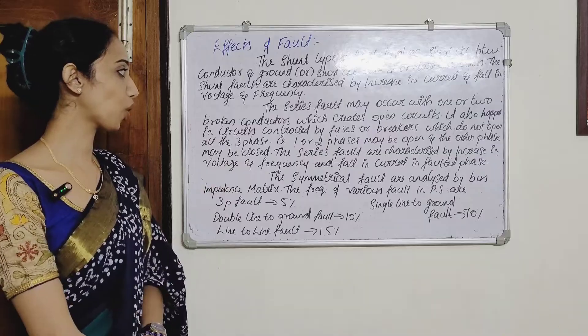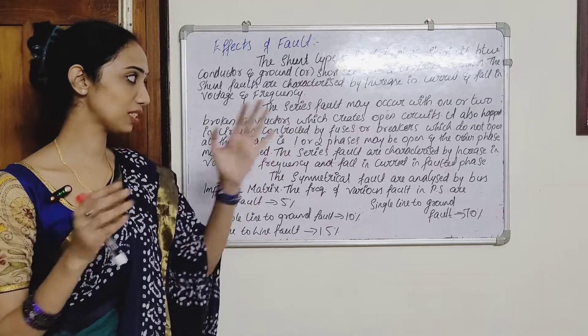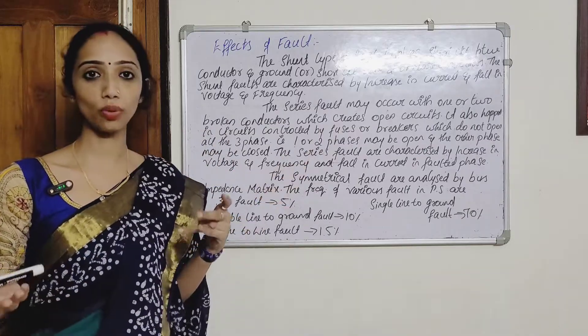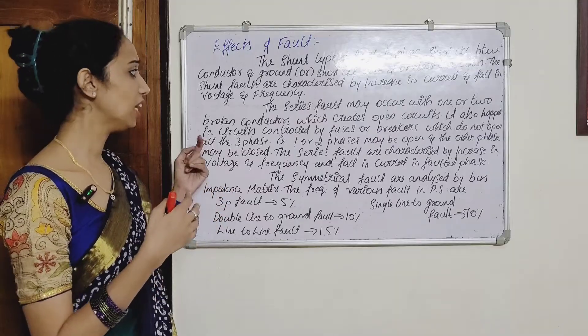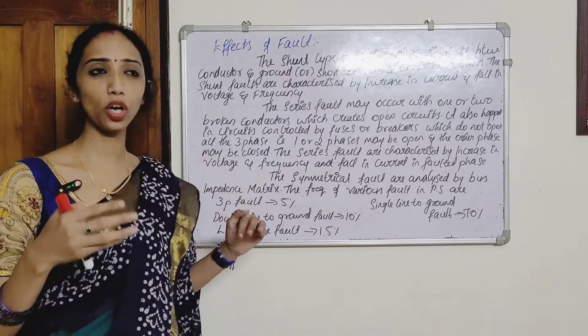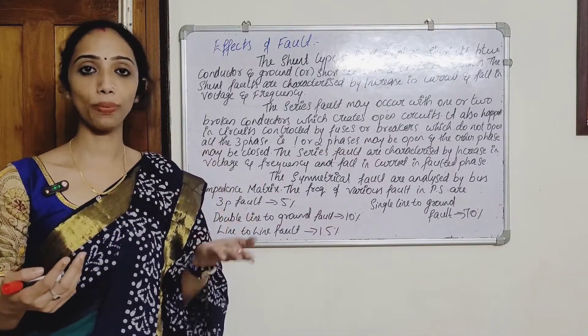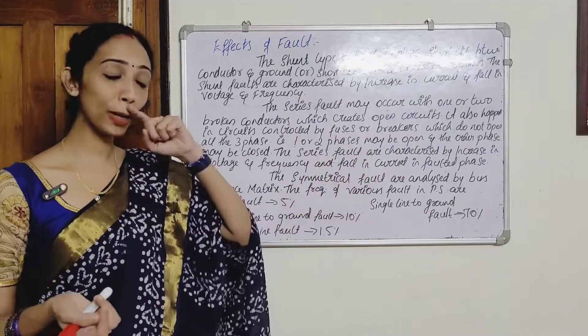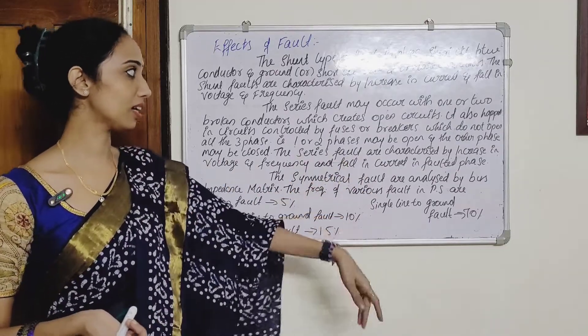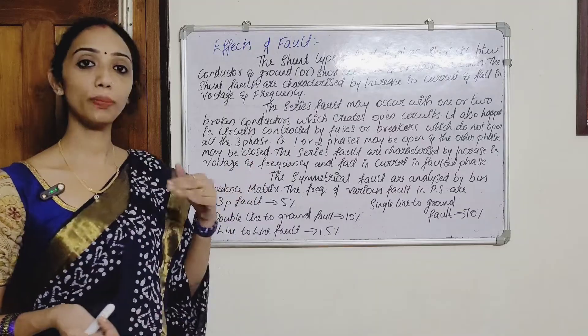Series fault may occur with one or two broken conductors which creates an open circuit. Series fault is also caused in circuits controlled by fuses or circuit breakers which do not open all three phases. As a result, one or two phases may be open while the other phase is closed. Series faults are characterized by an increase in voltage and frequency and a fall in current.